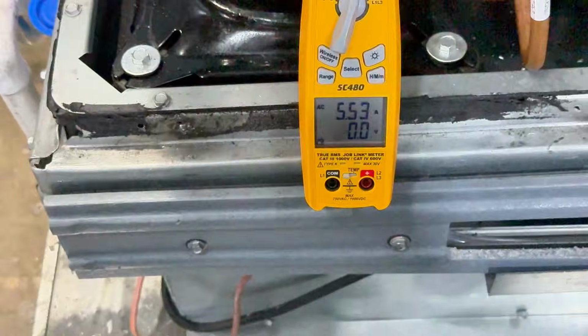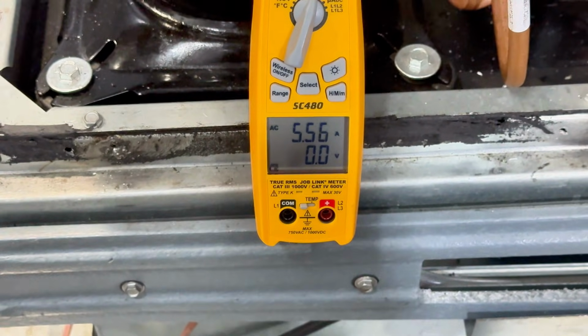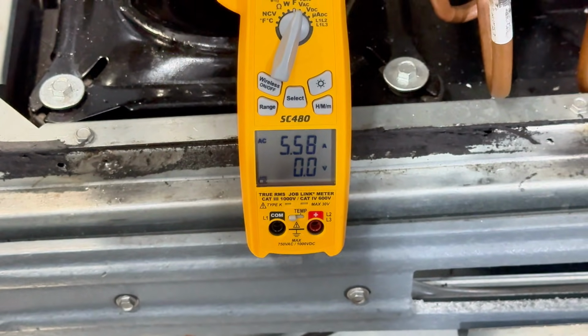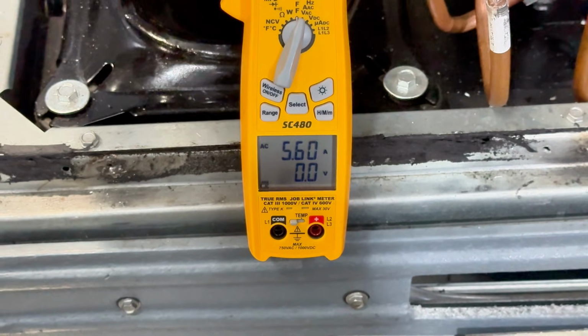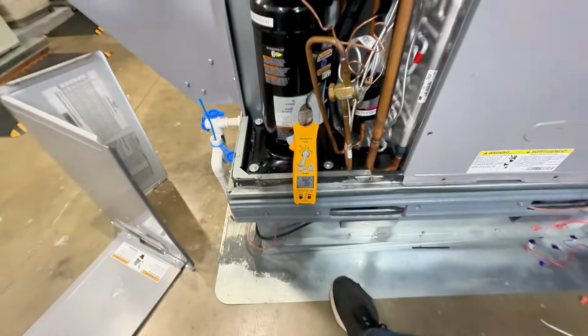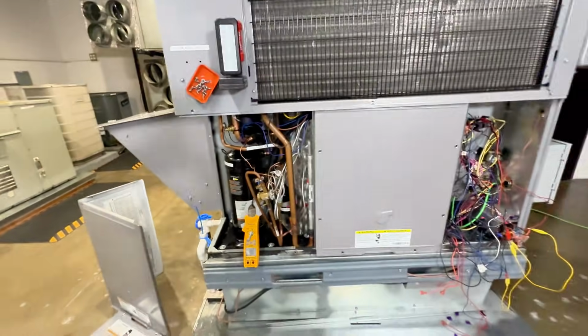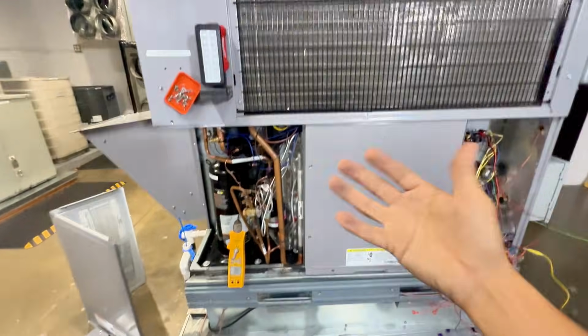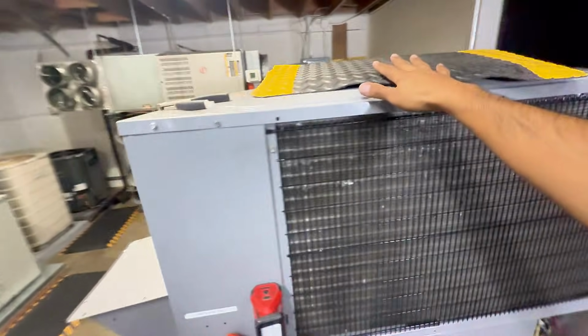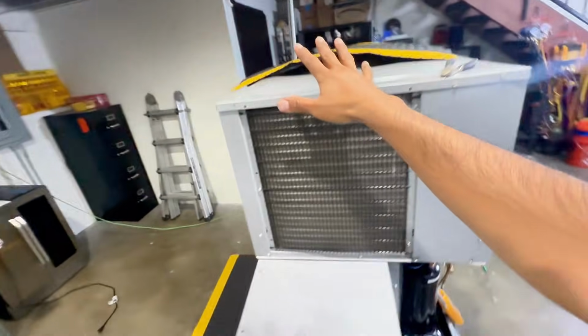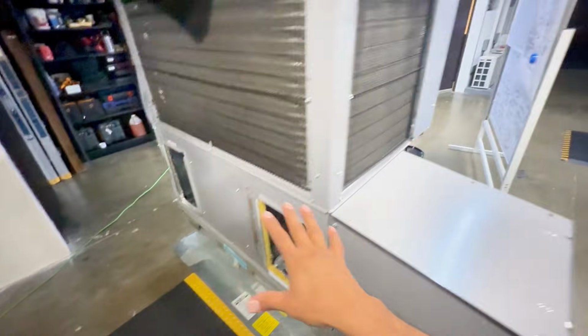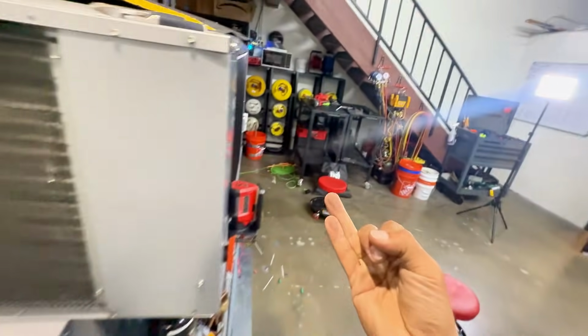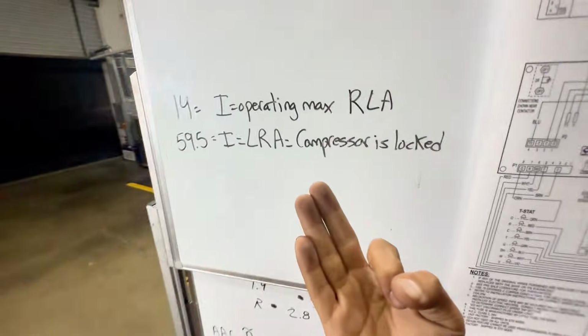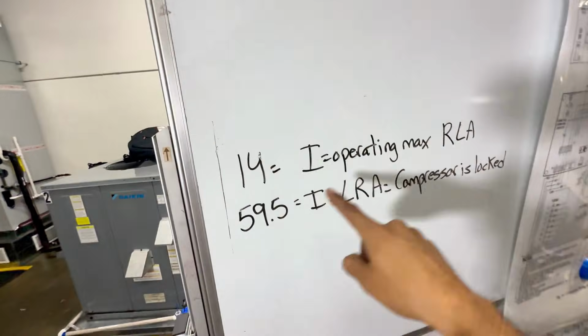In the case of this compressor, I'm already up almost half of 1 amp. It went from 4.8 to 5.6. It's almost 1 amp over. So that's the point I'm trying to get across. If you have a dirty condenser, you don't have good airflow. If it's overcharged or undercharged, that could impact the 14.